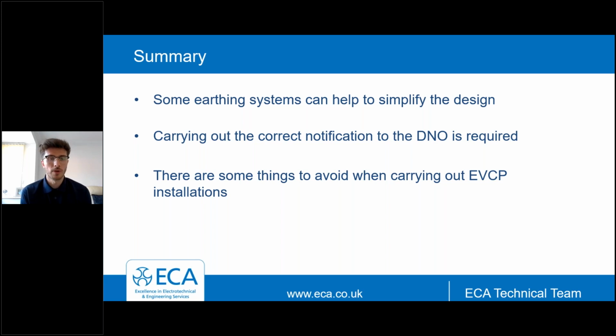I looked at the example around a TNS supply, where a reliable TNS supply was available with a dedicated maybe 11 kV transformer on site. I've also given examples on carrying out the correct notification process to the DNO, and this is a requirement, and we do get feedback that this is not always happening. Obviously, the DNO need to know what's going on to their network. And there are some things to potentially look at avoiding when carrying out EV charge point installations, or some stuff that requires some careful and further consideration.